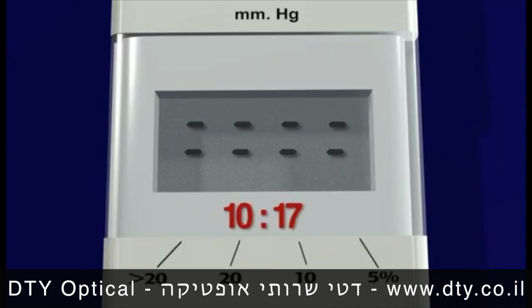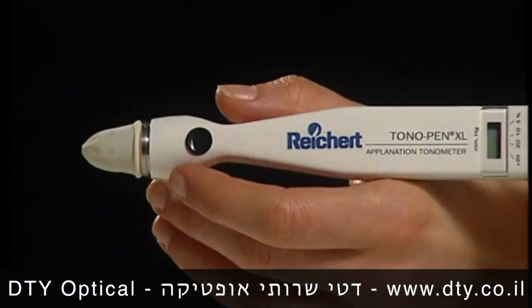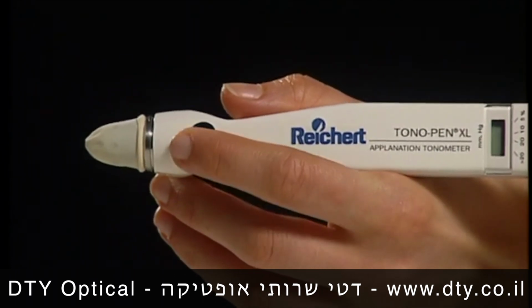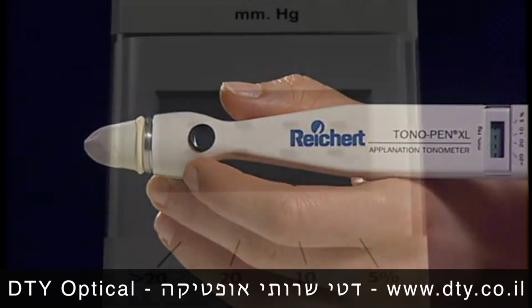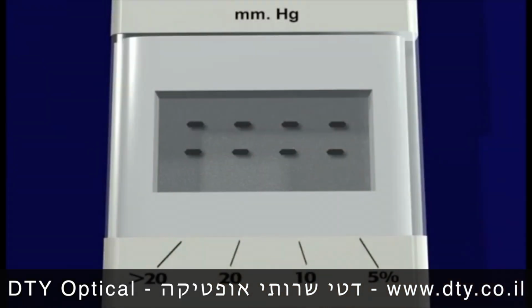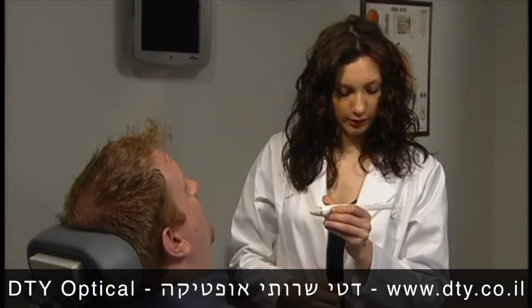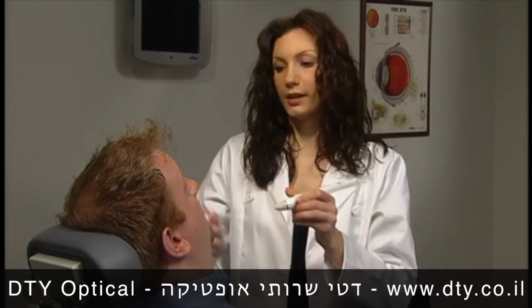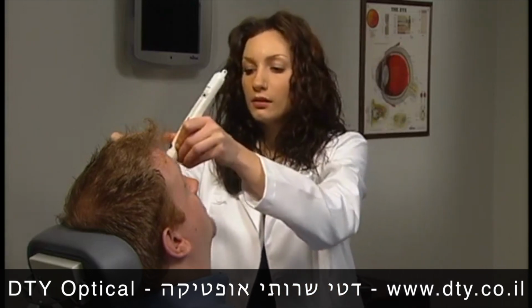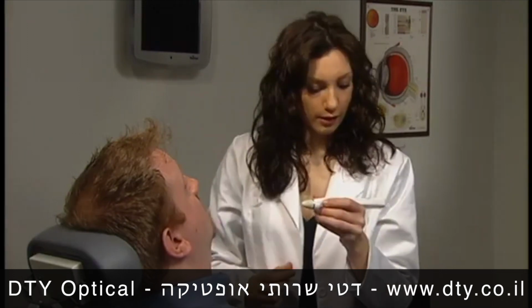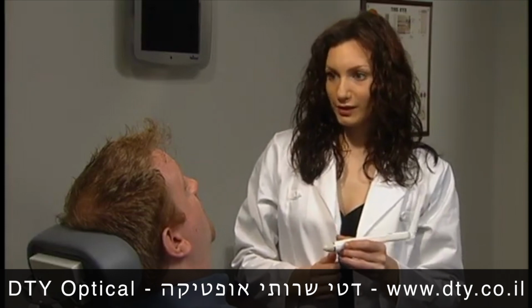If you exceed the 15 seconds, the instrument will beep and you will see a single line of dashes followed by a blank window. This indicates that the instrument is in battery-saving mode and will not measure. To reinitiate the measurement mode, simply press the operating button again, one time only. After the double row of dashes is displayed, proceed with the IOP measurement. Gently applanate or tap the transducer on the patient's anesthetized cornea. Ensure that the TonoPen XL tonometer is perpendicular to the cornea and that the taps are light, quick touches.